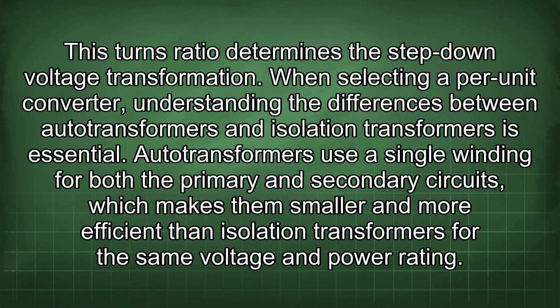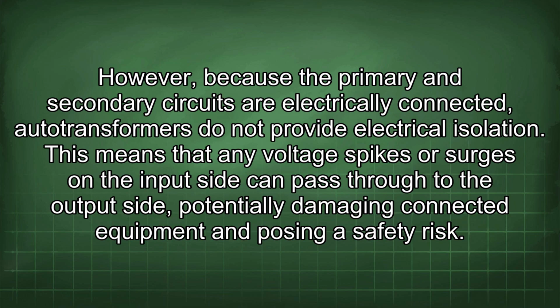When selecting a per unit converter, understanding the differences between autotransformers and isolation transformers is essential. Autotransformers use a single winding for both the primary and secondary circuits, which makes them smaller and more efficient than isolation transformers for the same voltage and power rating. However, because the primary and secondary circuits are electrically connected, autotransformers do not provide electrical isolation. This means that any voltage spikes or surges on the input side can pass through to the output side, potentially damaging connected equipment and posing a safety risk.